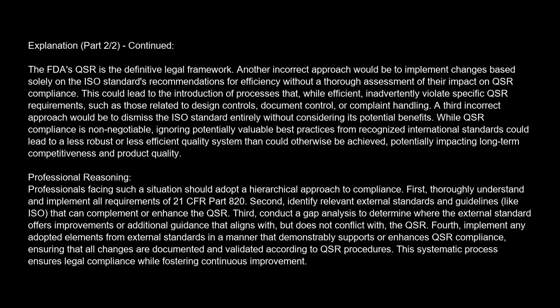Third, conduct a gap analysis to determine where the external standard offers improvements or additional guidance that aligns with, but does not conflict with, the QSR. Fourth, implement any adopted elements from external standards in a manner that demonstrably supports or enhances QSR compliance, ensuring that all changes are documented and validated according to QSR procedures. This systematic process ensures legal compliance while fostering continuous improvement.